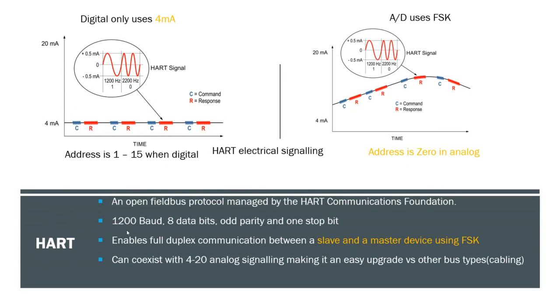So, more specs related to HART: 1200 baud, which is the speed at which it transmits information, as we discussed earlier. Baud is related to the size of the word, etc. The data package for HART contains 8 data bits, odd parity, and 1 stop bit.